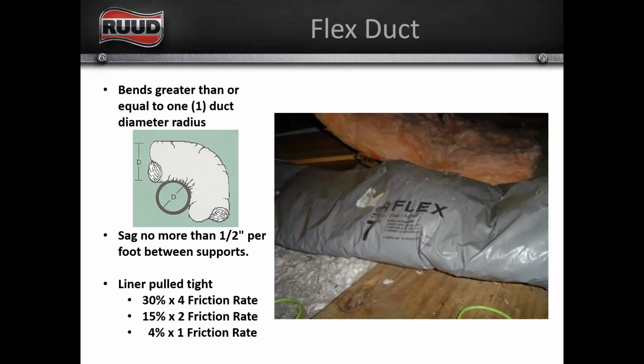And if you're not doing that, or if you go... I can't tell you how many times I've seen it, and I've done it, where you've got maybe 14 feet of flex in a run that could be half that, and it's just sort of laying up there. If you're having ductwork problems, the easiest thing to do is to find those issues and just cut that extra out, and shorten those runs.